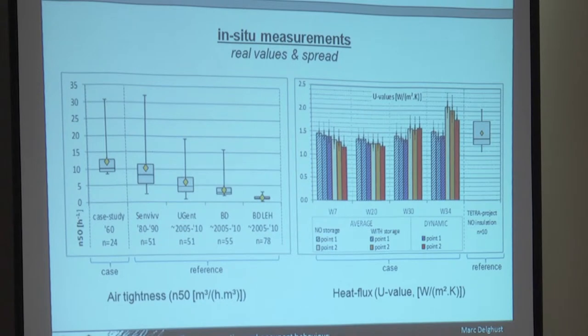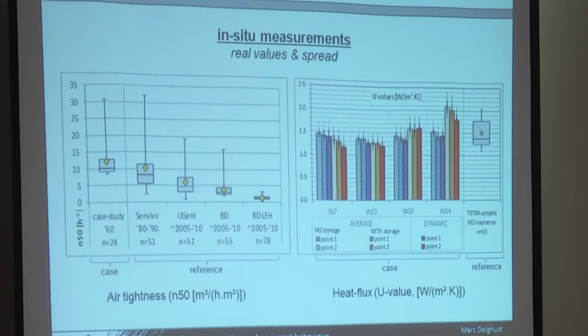For example, one of the things we measure is airtightness — because we don't want to use a default value in the calculation method; we want to know where the method fits. Here you see the airtightness of this neighbourhood. We assumed identical houses, but we found the airtightness N50 value going from around 7 to around 13 within the same neighbourhood. We compare that to reference buildings ordered chronologically from old houses from the 1980s in Belgium to recent houses in 2010 to passive houses — and it's quite in line with the evolution of airtightness in Belgium.